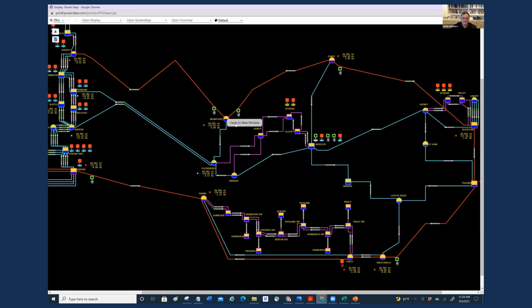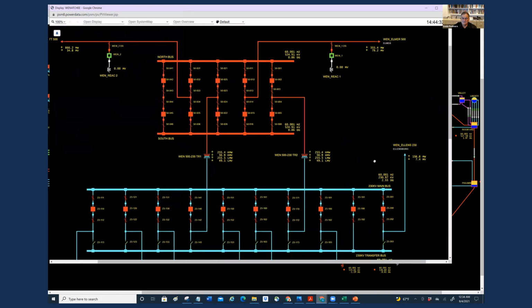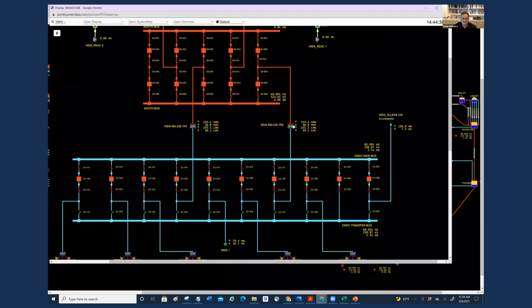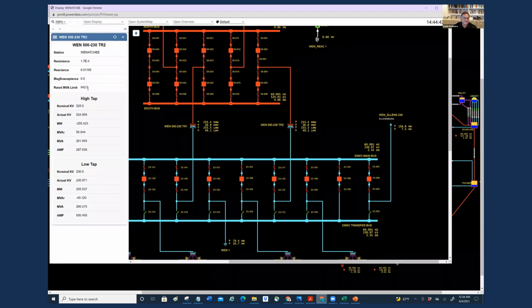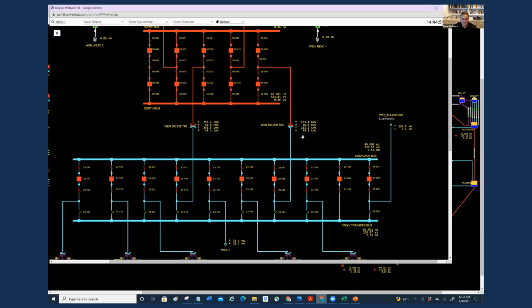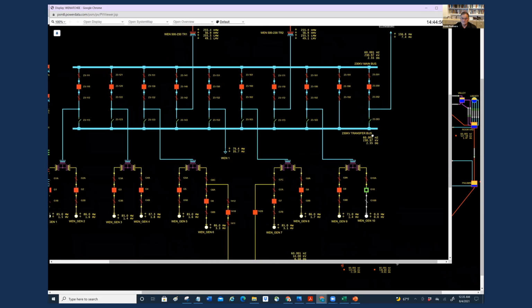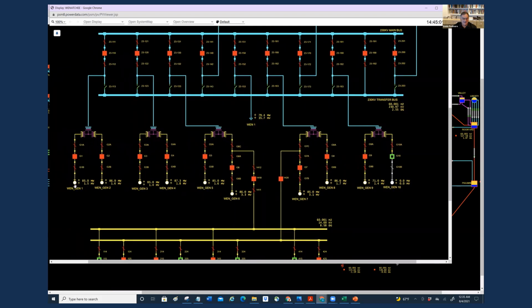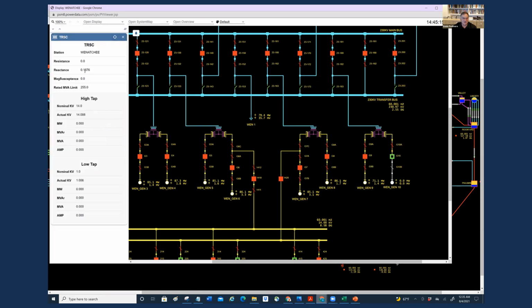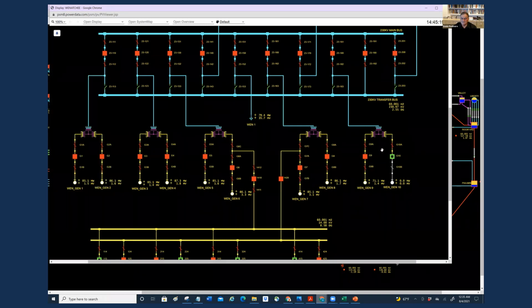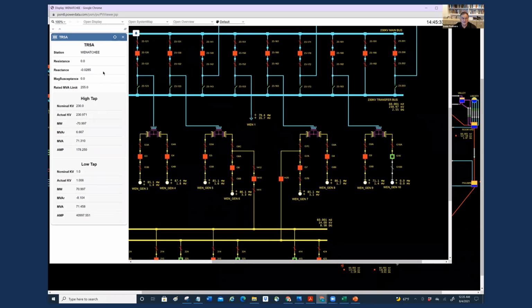And then at the Wenatchee station itself, we've got a 500 to 230 kV transformer. So we take the value of 0.011 and divide it by 0.00135 to get miles, and then we divide that by 2 because we've got 2 of these in parallel. Now, in the case of the generators at Wenatchee, we've actually got 10 of them, each of 100 megawatts. And this has a 3-winding transformer, which has a reactance of 0.187. That 3-winding transformer has been converted from a delta to a star configuration. And when you do that, you actually get a negative on this third winding.